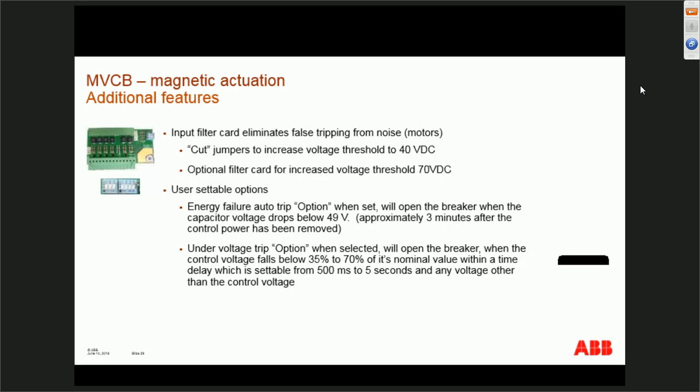in the closed position. Also, there's another switch called block breaker closed or block breaker open. If you have the under voltage set on and you send a signal to the breaker, you can have the breaker either do a close-open, or you can have the breaker stay in the open position just by a certain switch setting on the board. All of these are, of course, shown in the instruction manuals of all the associated products.